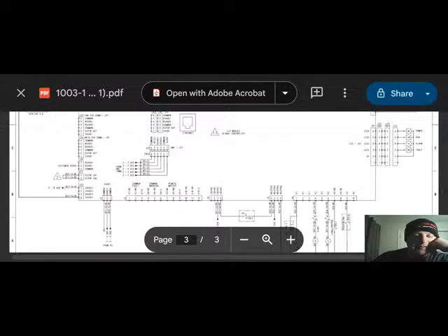So biggest thing to remember here is that this is a dry contact. There's no power supplied to these from the machine. You have to bring your own power source. So that pretty well covers the fault contacts and the warning contact. Like I said, they both basically look the same way. It's just one's triggered by a warning, one's triggered by a fault, and both are tied in however your little heart desires.